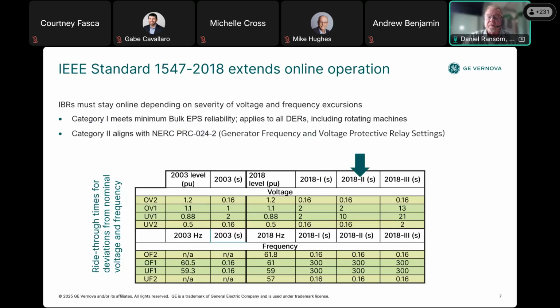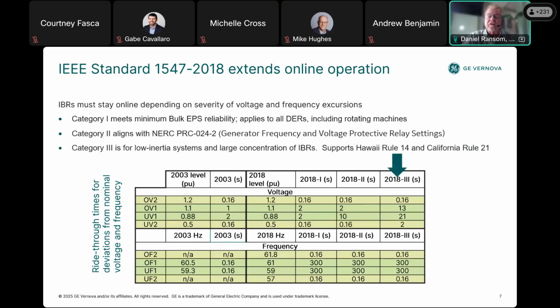We align with the NERC PRC-024-1. That's the generator frequency and voltage protective relay settings. And then category 3 is for low inertia systems, like a large concentration of IBRs. These can be supportive of the Hawaii Rule 14, the California Rule 21. As we can see, the times do not change much from 2003 to the 2018 category 1. However, the voltage and frequency ride-through requirements are now longer in the 2018 standard for voltage and frequency departures from nominal for category 2, and especially for category 3, as pointed out here.